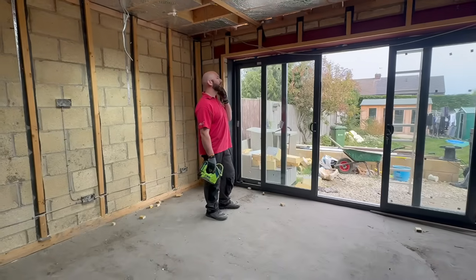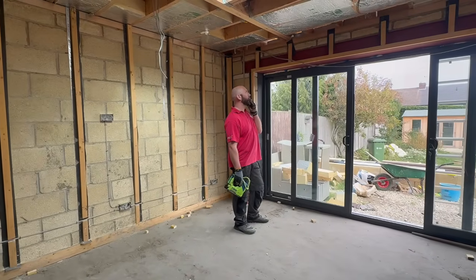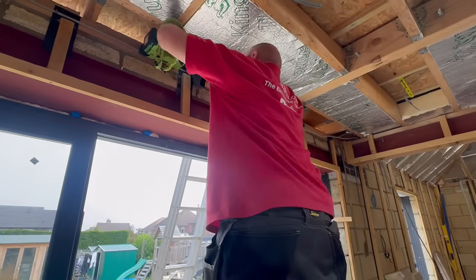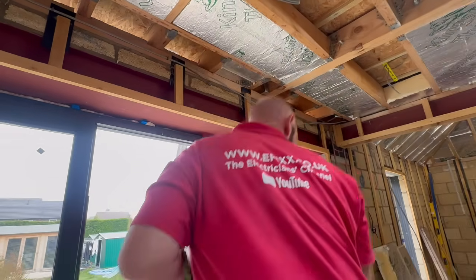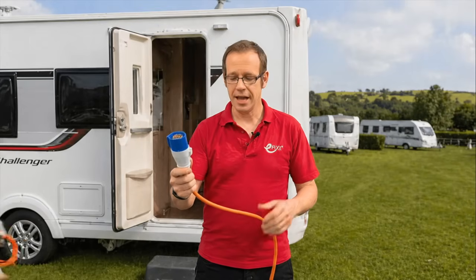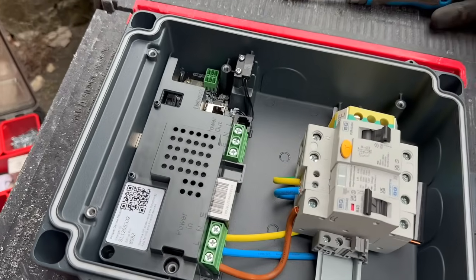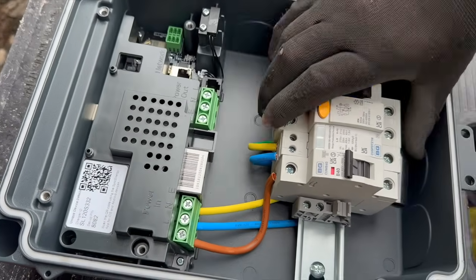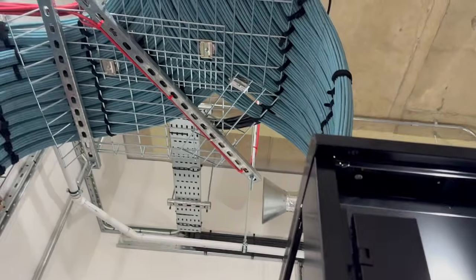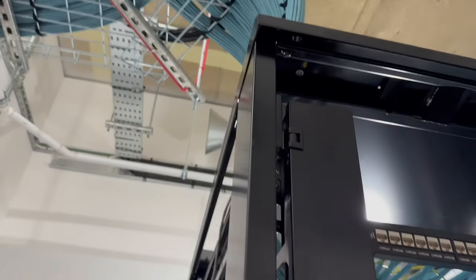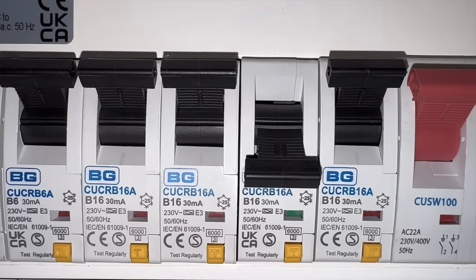So what has Amendment 4 actually changed? It has not completely rewritten how you install electrical systems, but it has tightened expectations across the board. It has clarified areas that were often misunderstood, and it has brought modern technologies fully into scope. Things like batteries, EV charging, power over Ethernet, and systems with multiple sources of supply. So this is no longer just about installing equipment correctly. It is about understanding how the system operates as a whole, how protection behaves, and how different parts of the installation interact with each other.